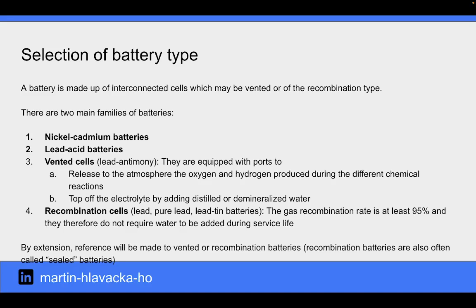There are two main families of batteries: nickel-cadmium batteries and lead-acid batteries. Vented cells are equipped with ports to release to the atmosphere the oxygen and hydrogen produced during the different chemical reactions, and top off the electrolyte by adding distilled or demineralized water. Recombination cells have a gas recombination rate of at least 95%, and they therefore do not require water to be added during service life.